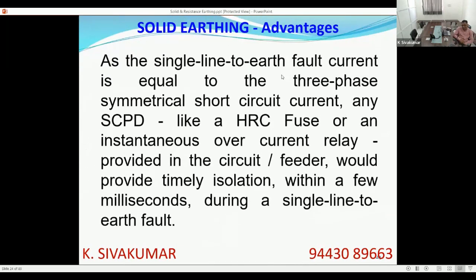Similarly, since a single phase line to earth fault current is equal to the three phase symmetrical short circuit current, you do not need any special sensitive earth fault protection devices. The current involved is in kiloampere generally. So when the current involved is in kiloamperes, any short circuit protective device in your system, like an HRC fuse or an instantaneous overcurrent relay, the 50 relay, any short circuit relay you provide in your system will act for this current and will isolate the fault very, very quickly.